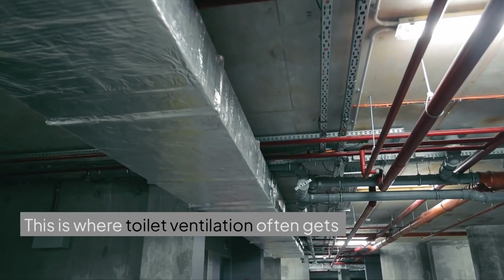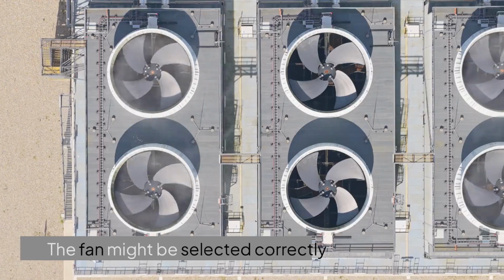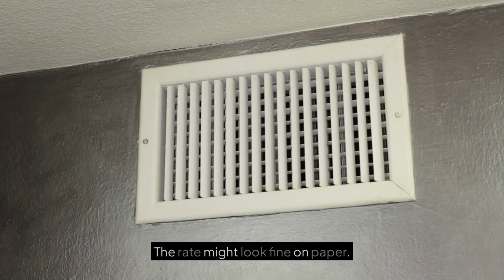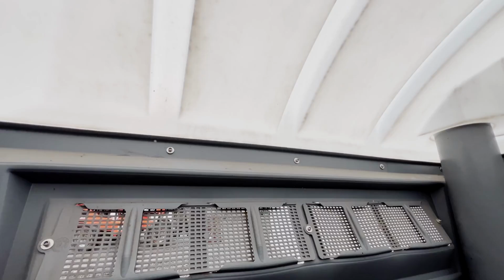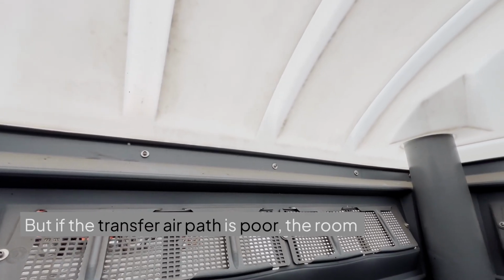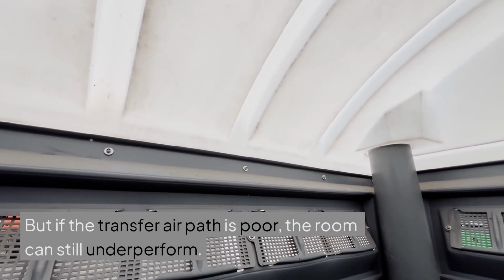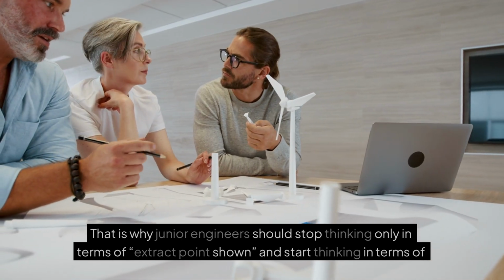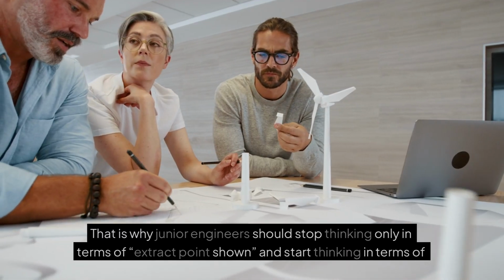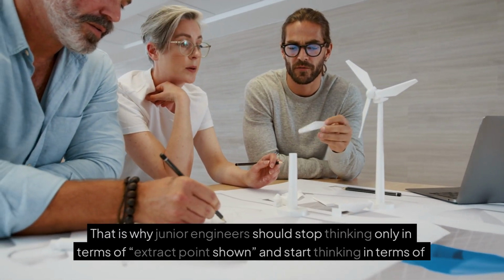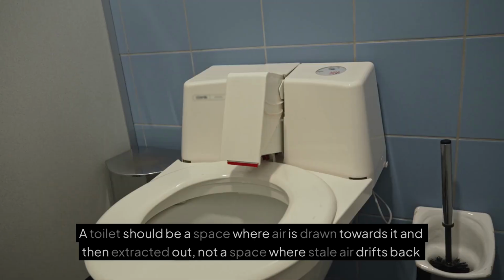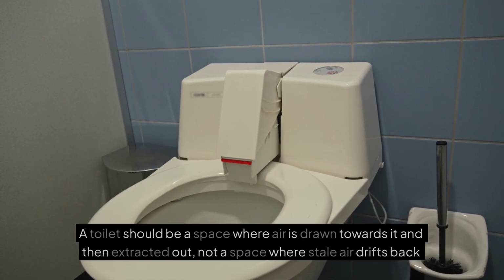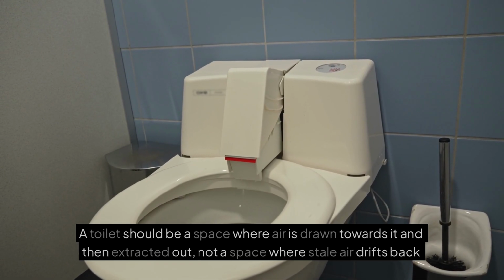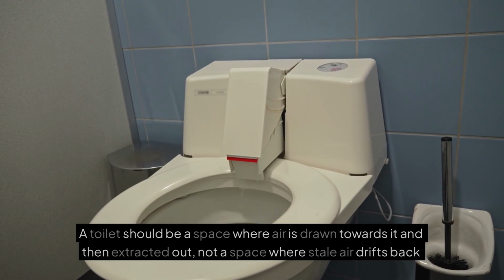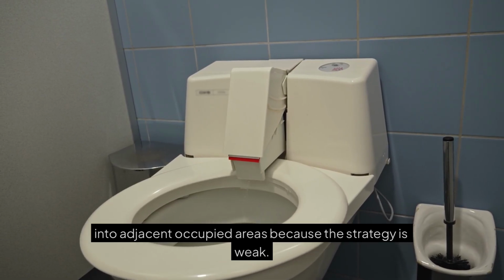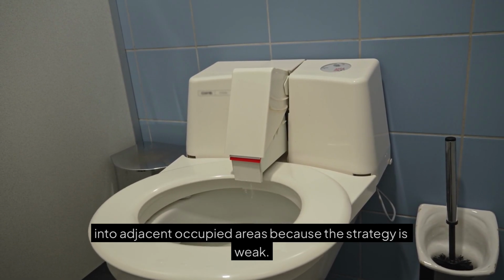This is where toilet ventilation often gets missed in practice. The fan might be selected correctly. The rate might look fine on paper. But if the transfer air path is poor, the room can still underperform. That is why junior engineers should stop thinking only in terms of extract point shown, and start thinking in terms of airflow direction. A toilet should be a space where air is drawn towards it and then extracted out, not a space where stale air drifts back into adjacent occupied areas because the strategy is weak.